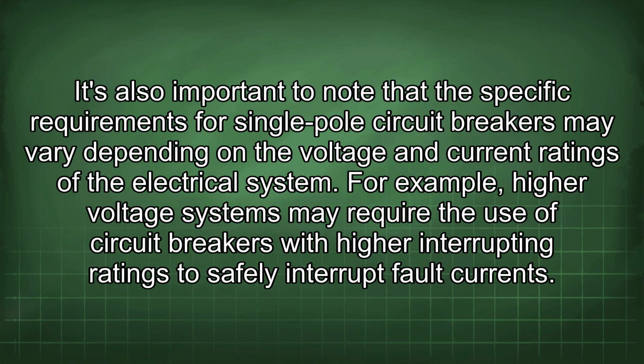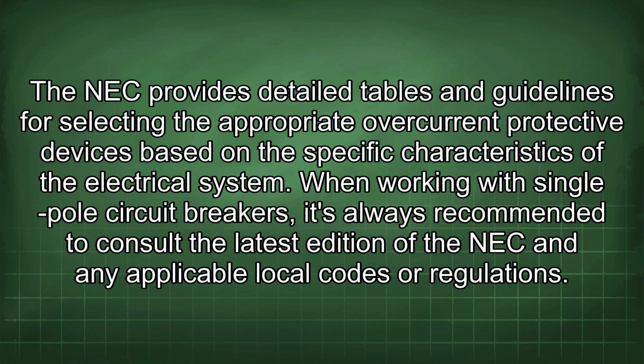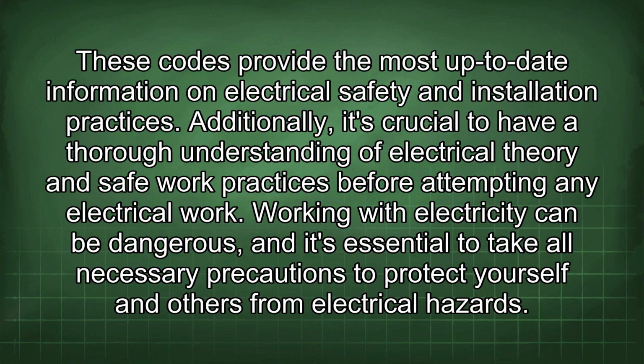It's also important to note that the specific requirements for single-pole circuit breakers may vary depending on the voltage and current ratings of the electrical system. For example, higher voltage systems may require the use of circuit breakers with higher interrupting ratings to safely interrupt fault currents. The NEC provides detailed tables and guidelines for selecting the appropriate overcurrent protective devices based on the specific characteristics of the electrical system. When working with single-pole circuit breakers, it's always recommended to consult the latest edition of the NEC and any applicable local codes or regulations. These codes provide the most up-to-date information on electrical safety and installation practices.